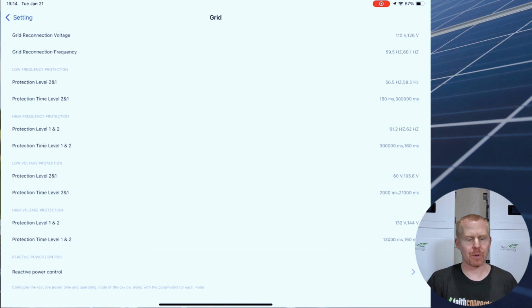So you can see there's multiple protection levels. You've got a high protection for frequency, a low protection for frequency, and then there's a level 1 protection and a level 2 protection. And then you can see the times that they have to hit that threshold. It can deal with 58.5 hertz for, what is it, 300 seconds, but then it can only handle 56.5 hertz for 160 milliseconds. And you can see it's got the same for voltage as well, levels and then thresholds.